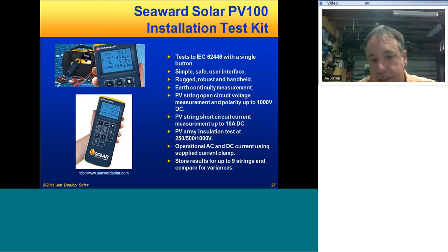Here's an example of the Seaward Solar PV100 installation test kit. This will do continuity tests, resistance tests. It'll do insulation resistance tests. It'll store measurements and download them via a USB port and give you all the stuff you need to produce this test report for the IEC standard. So you guys might want to take a look at that. The website's down there, SeawardSolar.com. Read a little bit more about this piece of test equipment.